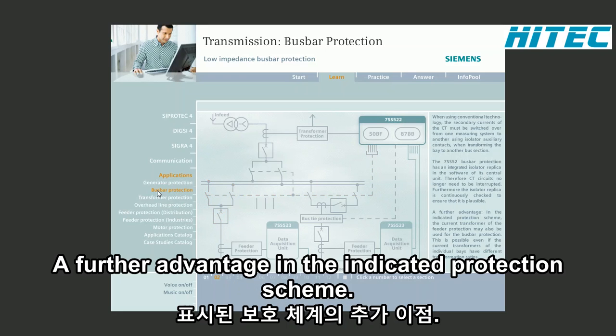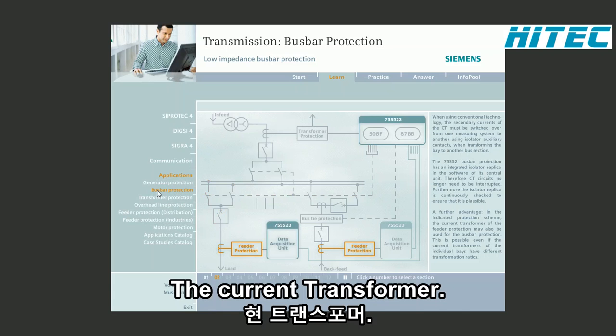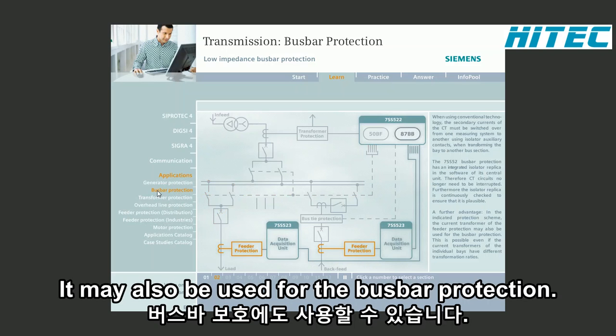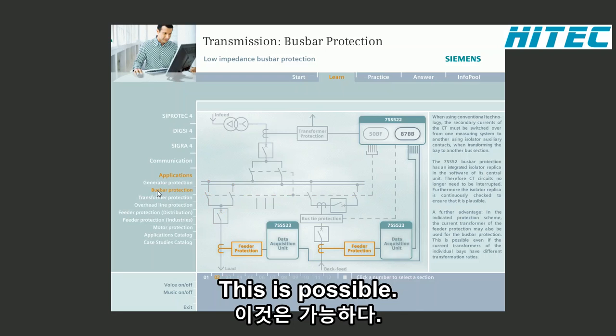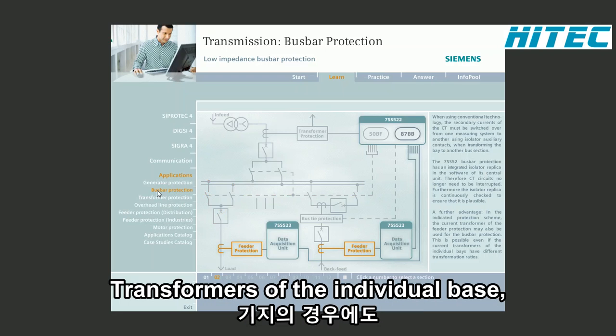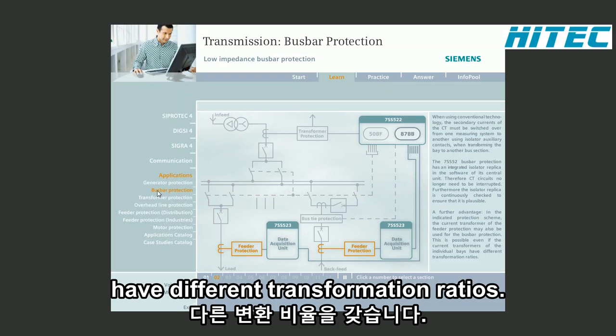A further advantage: in the indicated protection scheme, the current transformer of the feeder protection may also be used for the busbar protection. This is possible even if the current transformers of the individual bays have different transformation ratios.